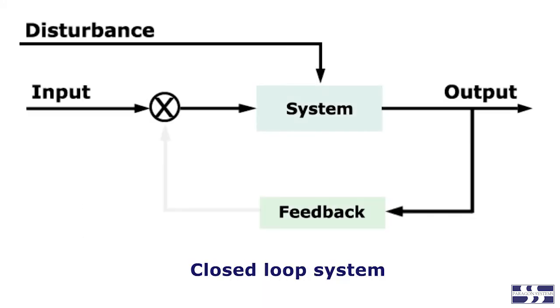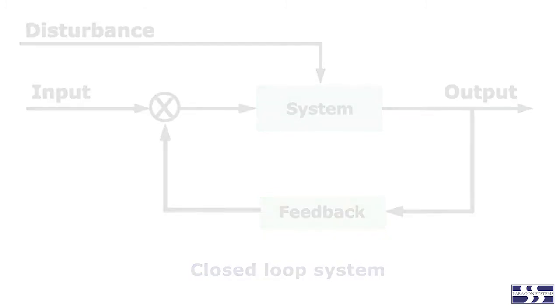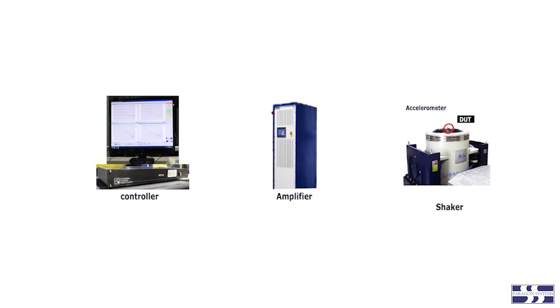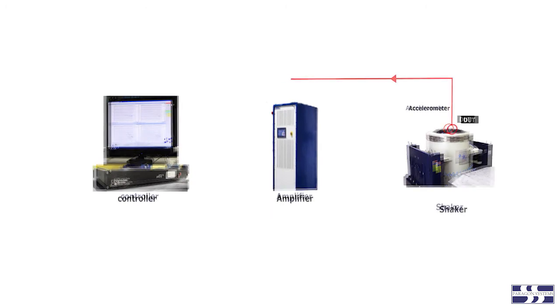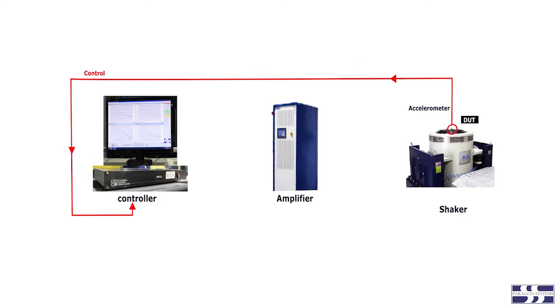The controller operates as a closed loop system. In its most basic form, this control system receives a signal from an accelerometer which is mounted to the shaker armature. From this signal, the controller determines the acceleration and frequency which are present at the armature, compares this with what they are supposed to be in the test profile, and adjusts an analog drive signal which feeds the amplifier.